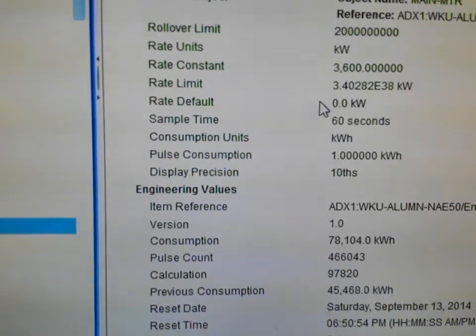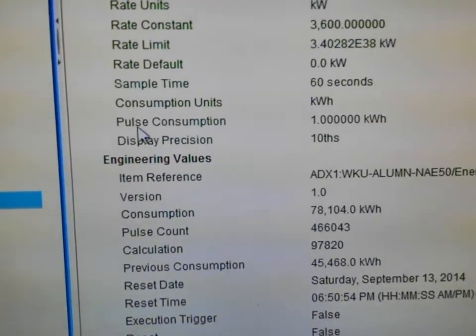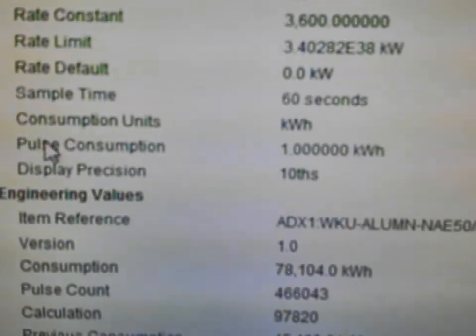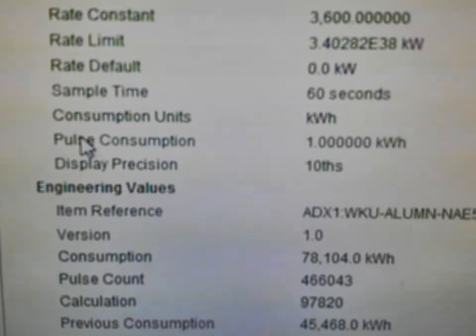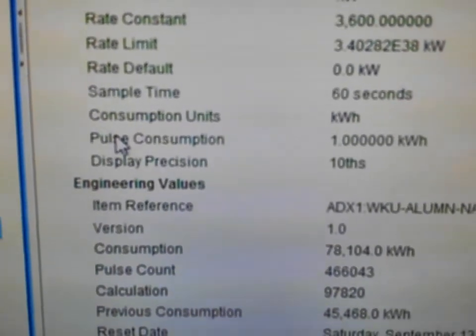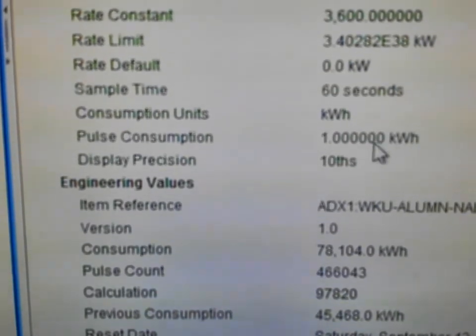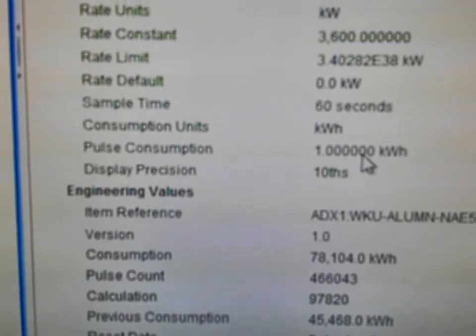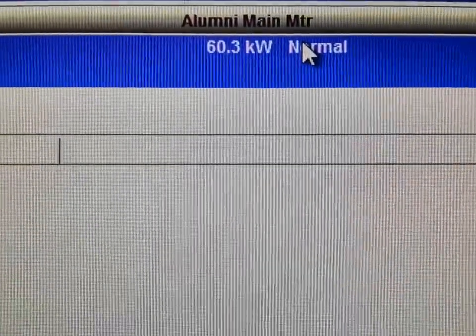When you set this up, you simply insert the object as we have done before. There's going to be your rate default and your sample time — for this it is 60 seconds. Pay very close attention to the pulse consumption field. Inside your meter itself there will be a configuration that allows you to set how many pulses are sent out per kilowatt. This value in Metasys has to match that value in the meter. If it does not match, you will not get an accurate reading. This meter will record and display the current usage for the particular power meter it is linked to through that accumulator.